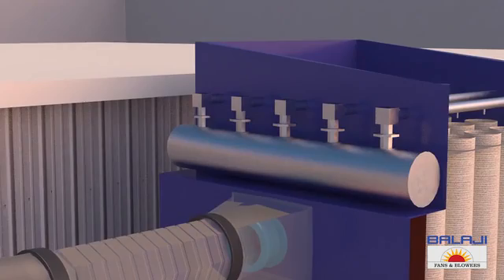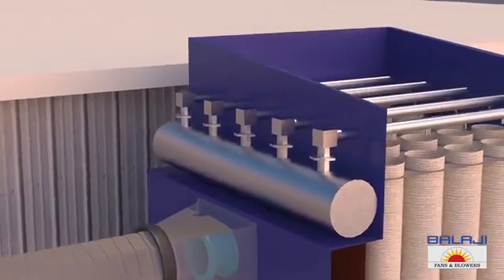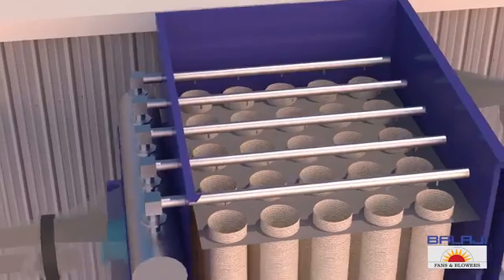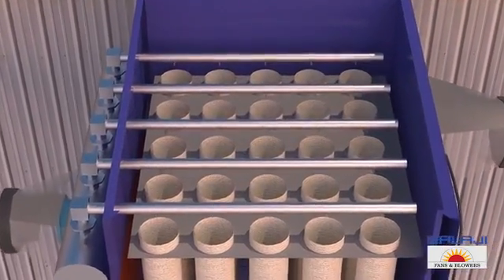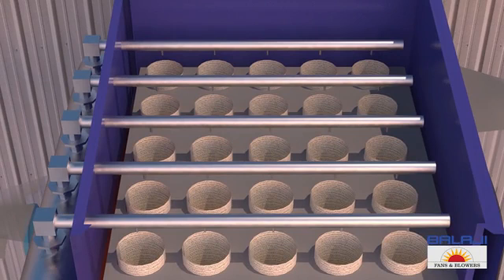Air stored in the header is released, which is carried by the blow pipes. This high-pressure air is then released in the filter bags one row at a time. This air passing through the filter bags releases the deposited dust.